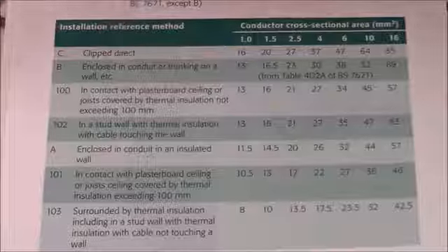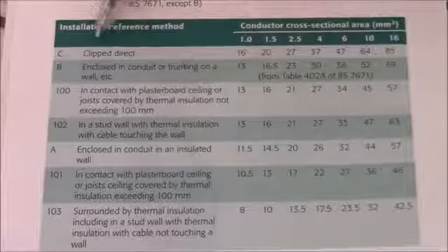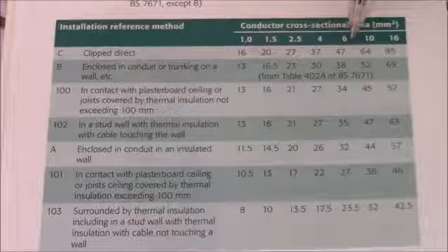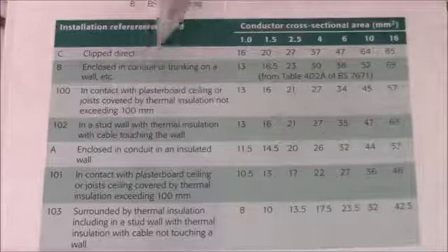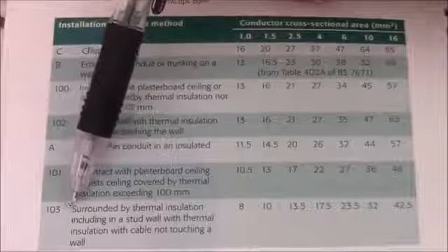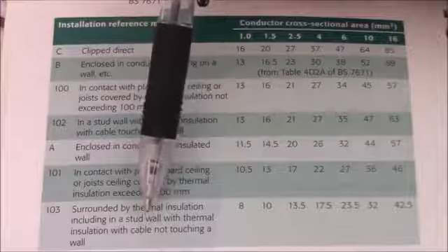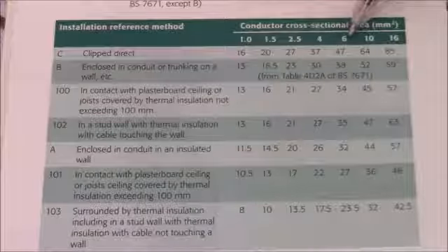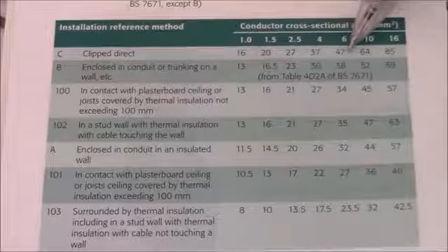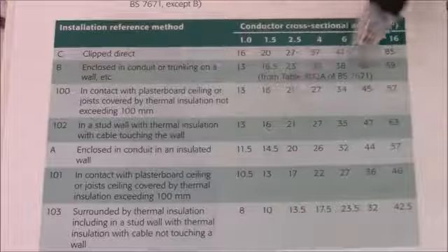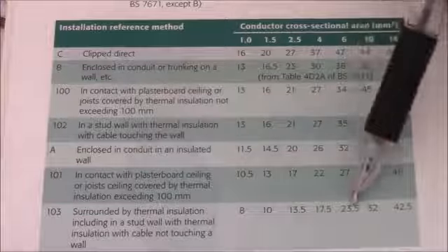The reference methods are few. The rating of the cables I gave you is just for when they are clipped direct straight to the wall and don't touch any insulation. So let's see reference method 103. This is surrounded by thermal insulation completely, so basically from every side. Now look at the 6 mil cable. When you clip it direct to the wall, the rating is 47 amps, but when you put it into insulation and wrap it completely, the rating falls down to 23.5 amps.